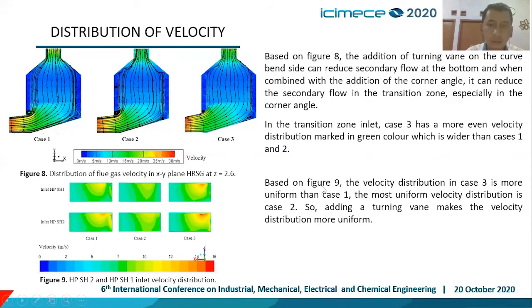Based on figure 9, the velocity distribution in case 3 is more uniform than case 1. We can see the yellow color is wider than case 1, even though in case 3 there is a red color wider than case 1. The most uniform velocity distribution is in case 2. So adding a turning vane makes the velocity distribution at the inlet of high pressure superheater 2 more uniform.